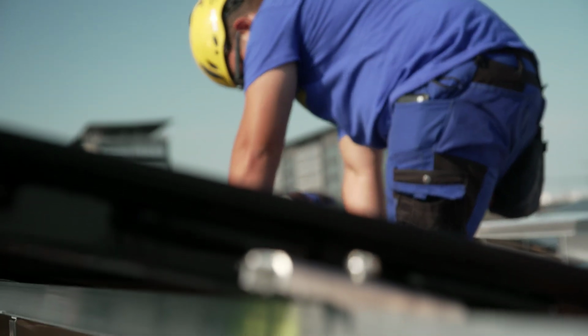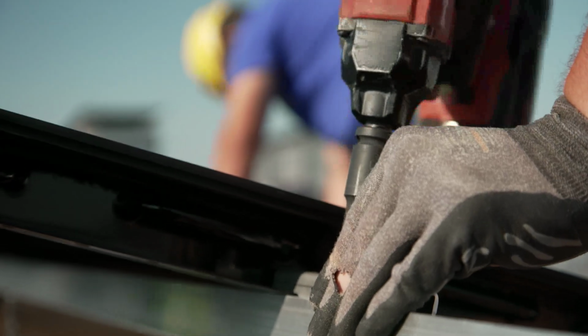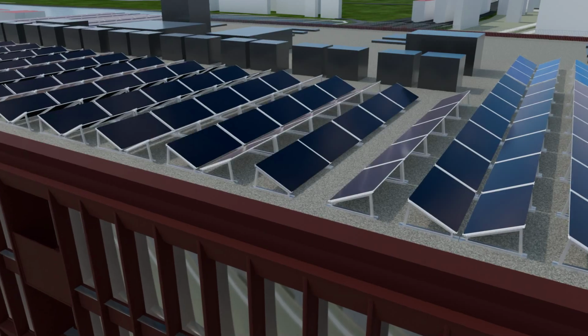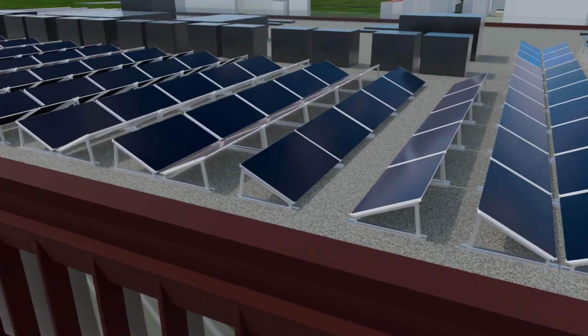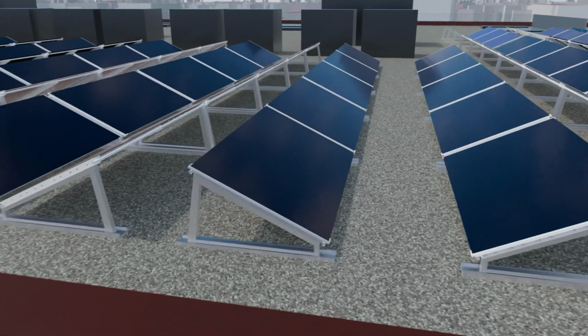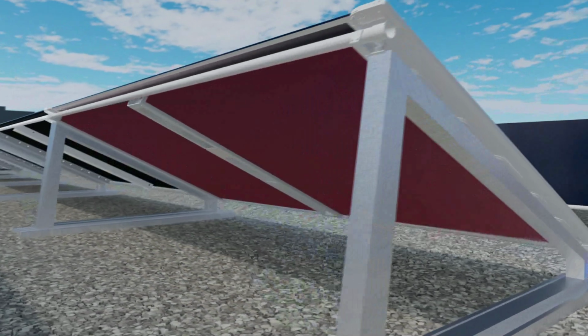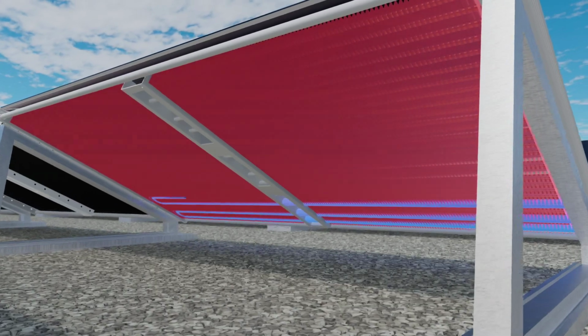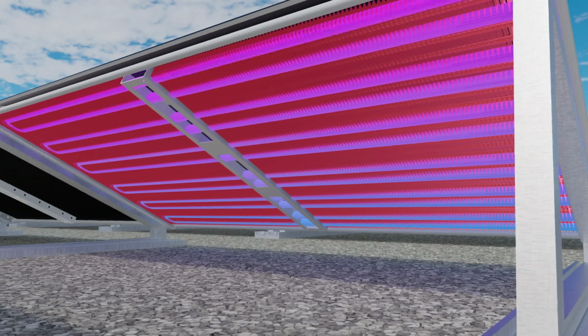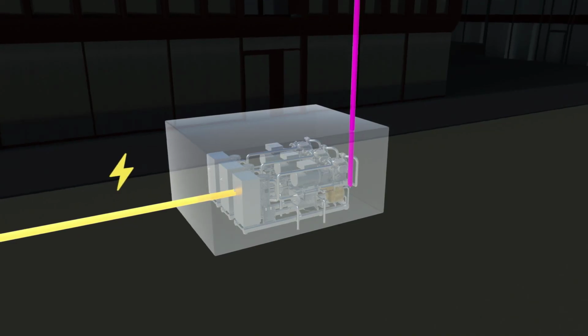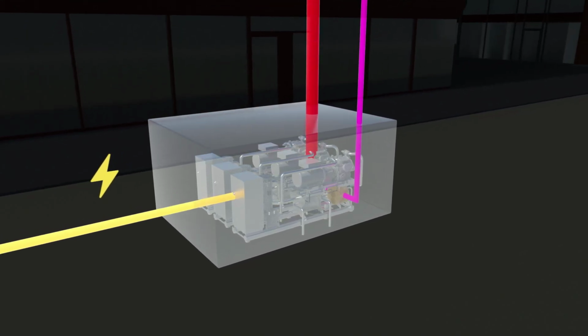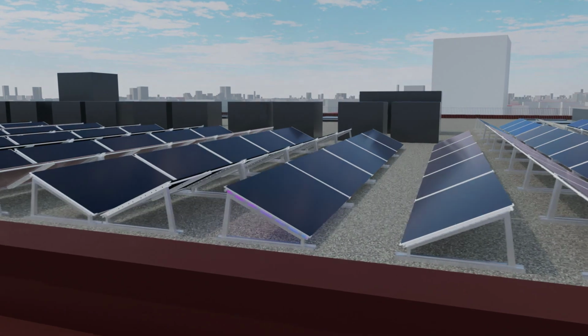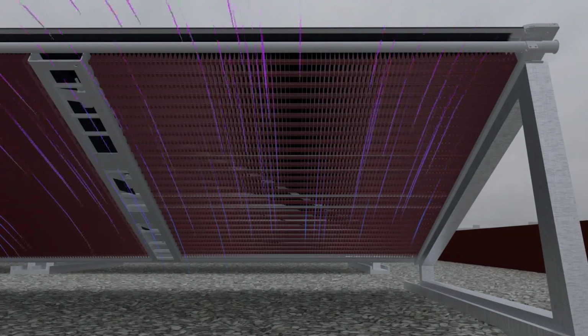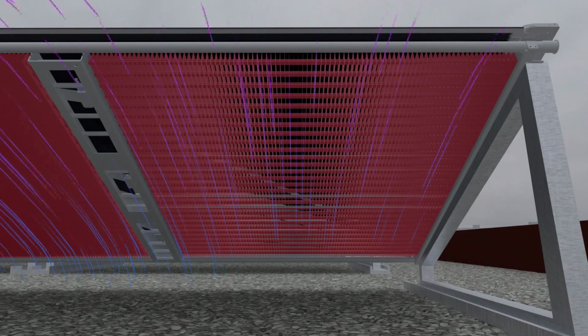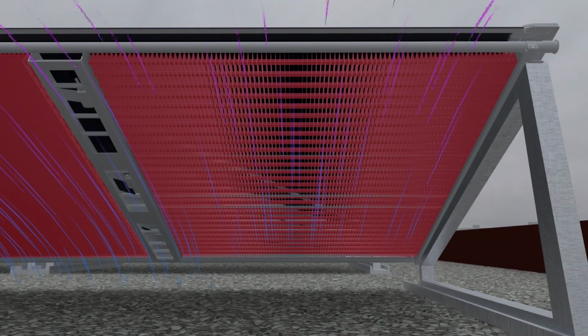The PVT modules are a recent innovation, combining solar cells and thermally open solar collectors. When the sun shines, the cells produce solar power, and the entire module heats up. There is also a heat exchanger on the back of the PV cells. The brine flows through this heat exchanger as well. The heat pumps then use this thermal energy to heat the building. But even when the sun is not shining, the collectors can still use renewable energy. The heat exchangers extract heat from the ambient air. The energy that is generated can also be used by the heat pump to heat the building.